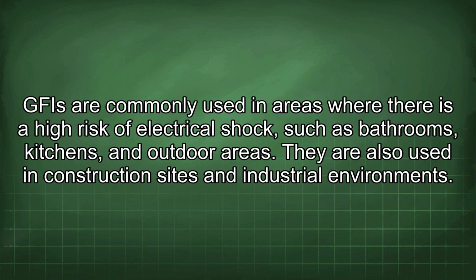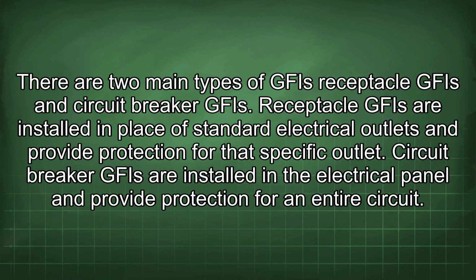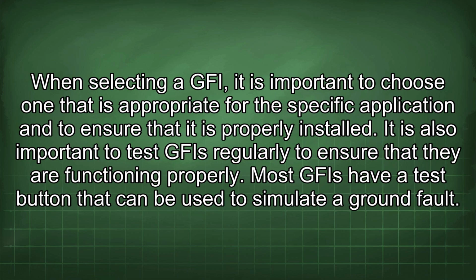GFI are commonly used in areas where there is a high risk of electrical shock, such as bathrooms, kitchens, and outdoor areas. They are also used in construction sites and industrial environments. There are two main types of GFI: receptacle GFI and circuit breaker GFI. Receptacle GFI are installed in place of standard electrical outlets and provide protection for that specific outlet. Circuit breaker GFI are installed in the electrical panel and provide protection for an entire circuit. When selecting a GFI, it is important to choose one that is appropriate for the specific application and to ensure that it is properly installed.